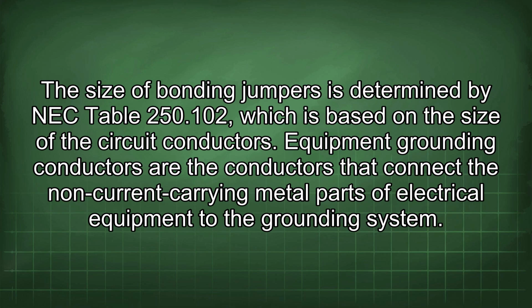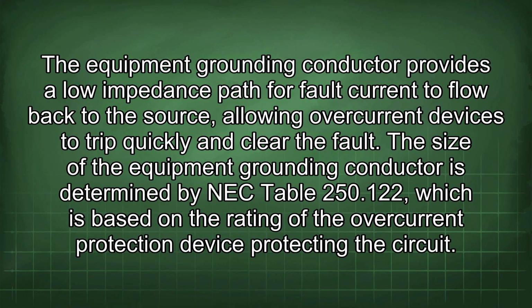Equipment grounding conductors are the conductors that connect the non-current carrying metal parts of electrical equipment to the grounding system. The equipment grounding conductor provides a low impedance path for fault current to flow back to the source, allowing overcurrent devices to trip quickly and clear the fault. The size of the equipment grounding conductor is determined by NEC Table 250.122, which is based on the rating of the overcurrent protection device protecting the circuit.